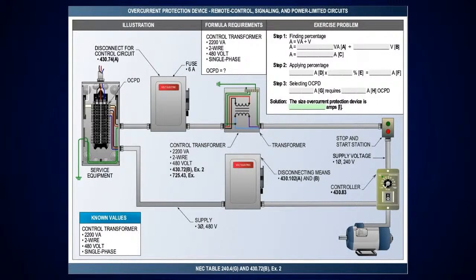And then you got the same thing here. You got your control conductors, you got a control transformer there. Well, what do I have? I have a 2200 VA transformer. It's 480 volts. You're going to divide into that, get your amperage, then you're going to go look at table 450.3B to get the percentage. So in this case, if I was below 2 amps, then I'd take it at 300%. See that? And that's where you're going to look at table 450.3B.